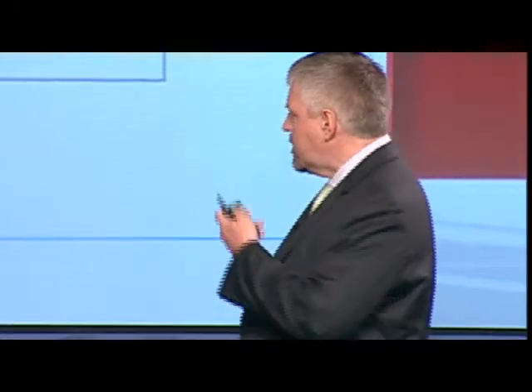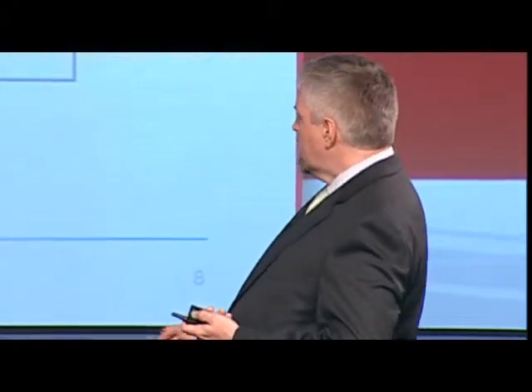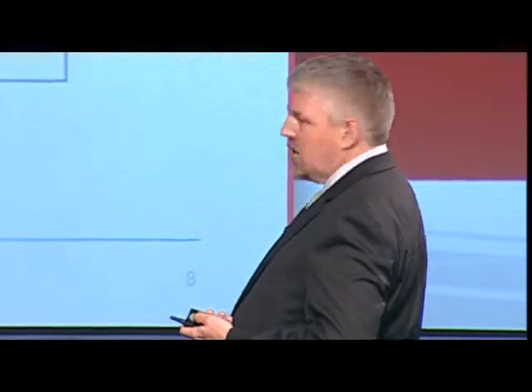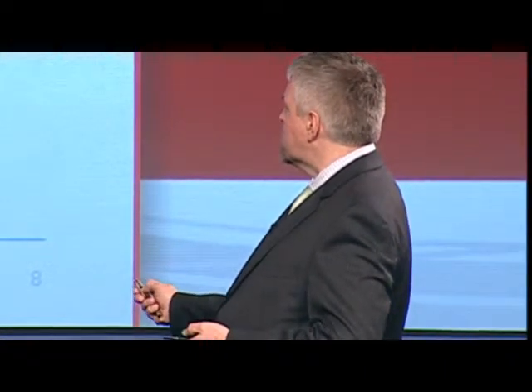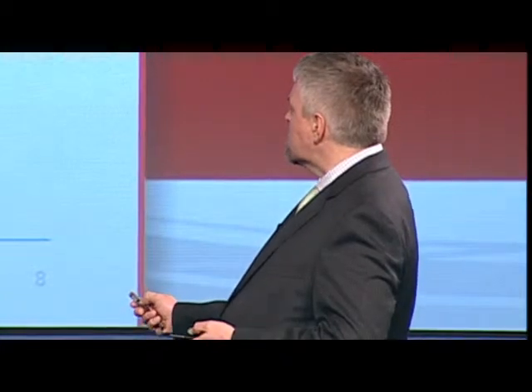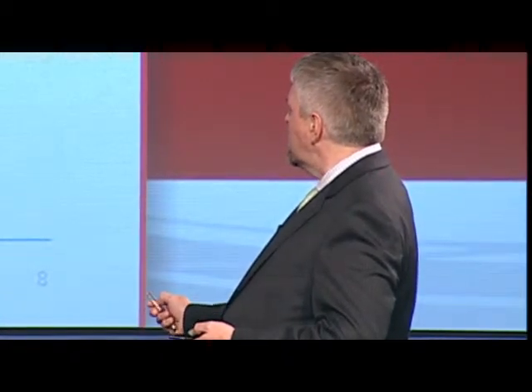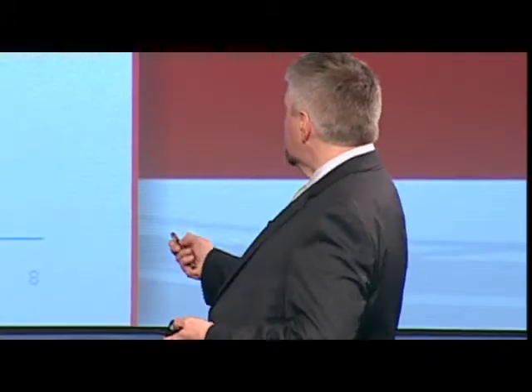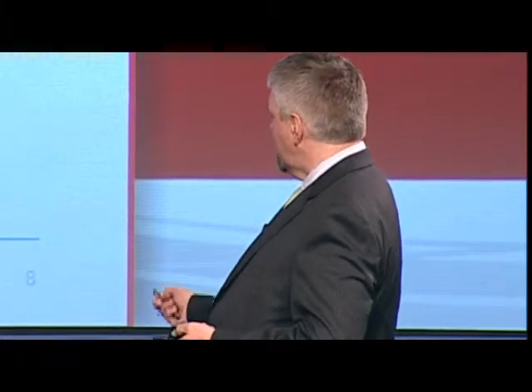Let me break it apart a bit more clearly. Putting the test on the bottom axis and CPU utilization on the side, you can see this line represents blades idling from 60 Fahrenheit all the way to 90 Fahrenheit. Then 25%, 50%, 75%, and 100% consumption. There is a slight trend upward at the high end in the 25% line. There's also a gap missing here — I'll show you on the next page why that happened, as we actually had to abort part of the test.